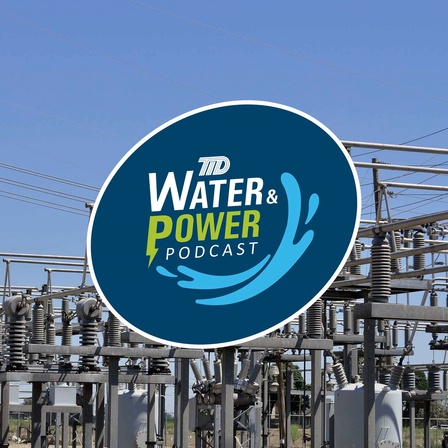Substations can really vary in size, and it depends on the system and their standards. For TID specifically, we have more of a rigid bus design, with a footprint we're looking to achieve. We want a parcel of land that allows access and maneuverability within the substation—room to bring in large equipment like transformers, and to cross canals in some cases. I'd say a 3-acre footprint is the minimum you'd want, and hopefully more from there. Really, we'll take what we can get.